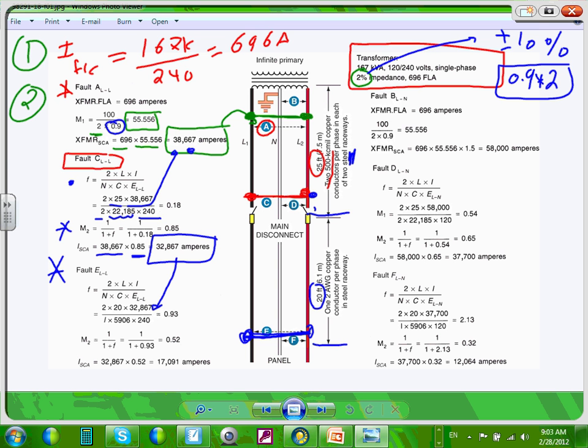Okay, now let's see, guys. I have 2 AWG copper conductor in steel. Can you find me the C factor for number 2 steel from this table that we're looking at? Number 2 steel. What's the factor for steel? Number 2 conductor under 600 volt. 5,906. Thank you. 5906. That's the C factor for this conductor. Can you guys see where the conductor is? Right here. Number 2. How many of these conductors, Nick? 1. So that's where the 1 here comes from. Can you guys see that 1? Okay, so it will knock it down to 93%. So you grab it and put it back, and with this factor, whatever the short circuit is here, it's going to be cut by almost half. So then you multiply the available short circuit by 0.52. It will give you, right at this point, we went down to 17,000.